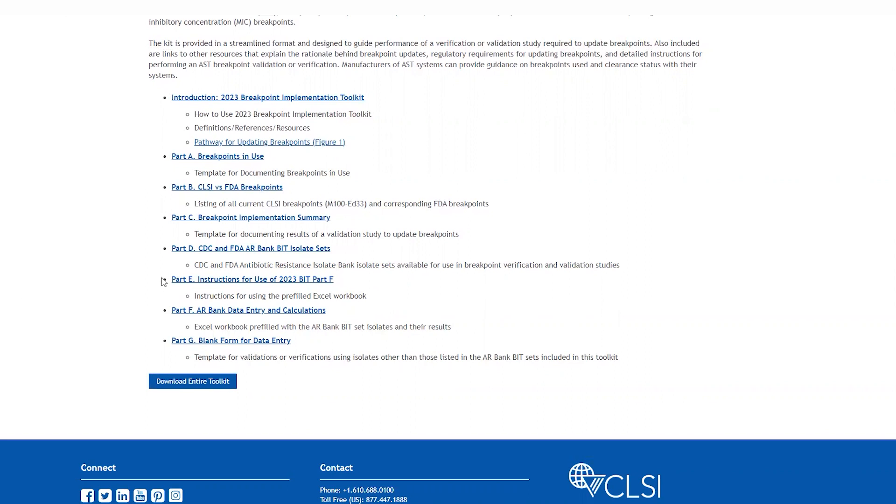Part E is the instructions for use and part F is an Excel pre-filled workbook to complete your verification or validation study calculations using these AR bank isolates, including calculations for categorical agreement, essential agreement, and calculation of categorical error types. The Excel spreadsheet has underlying formulas to help calculate these performance characteristics and they're associated with the CDC FDA AR bank isolate sets.